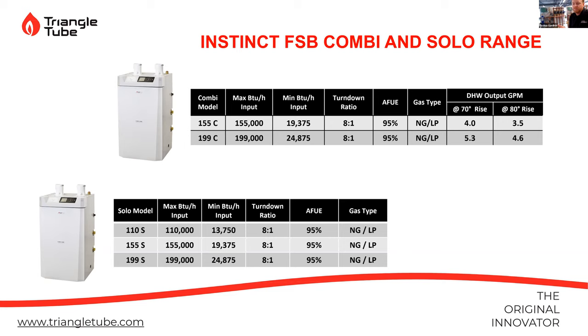The boiler itself is the same boiler. We have the same components, actually the same parts. The cabinet's a little bit different and the piping arrangement's a little bit different inside. But with all of our floor boilers, your primary piping's done. So the boiler comes out of the box with a Caleffi low loss header installed in there. So all you're gonna do is take that Caleffi low loss header, put it on either the right side or left side. The boiler can be piped either way. It's universal. On the floor boilers, you have your gas, your water, your condensate coming off on either side, and then your domestic connections and your vent terminations come directly off the top.